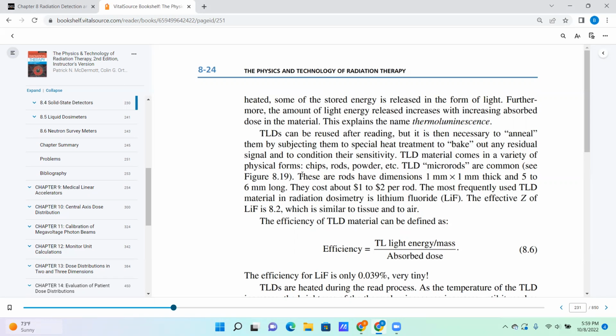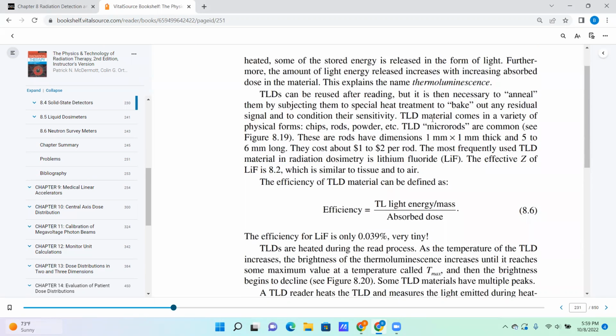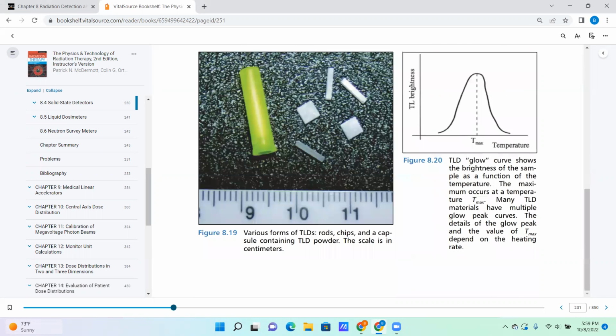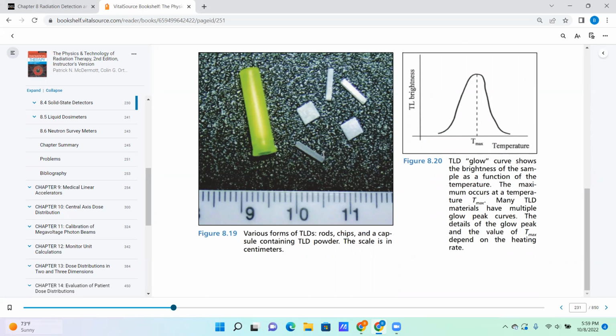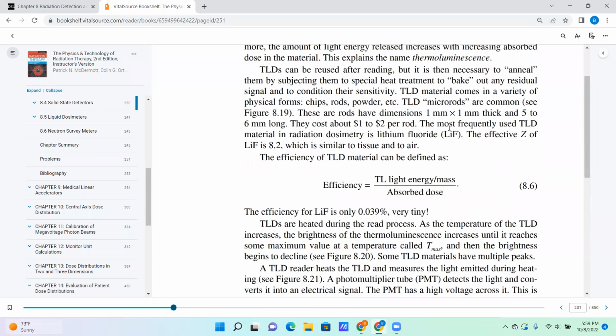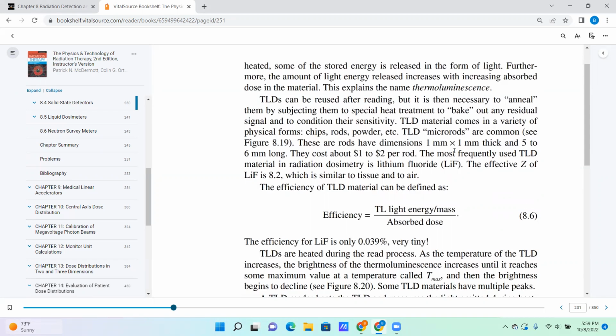There you go. TLDs can be reused after reading, but it is necessary to anneal them by subjecting them to special heat treatment to bake out any residual signal and to condition their sensitivity. TLD materials come in a variety of physical forms: chips, rods, powders, etc. TLD micro rods are common. Figure 8.19. These guys. And these rods, these are rods.